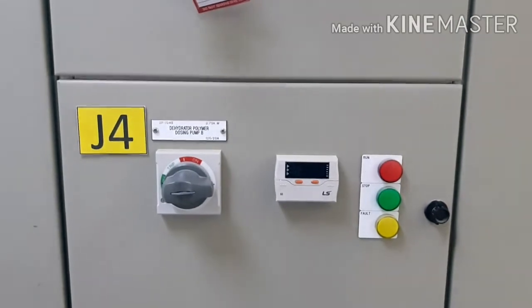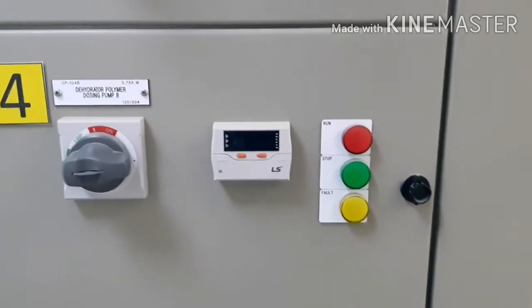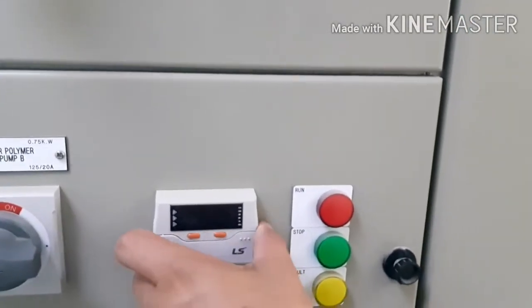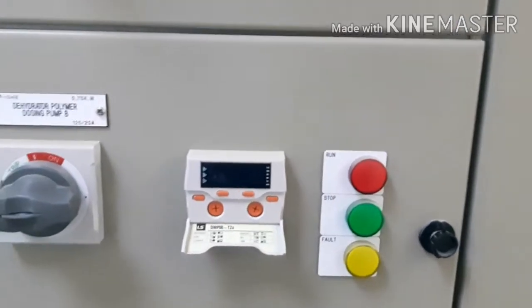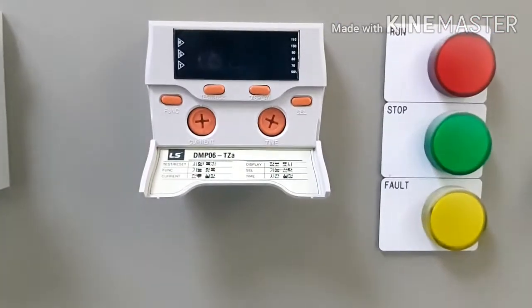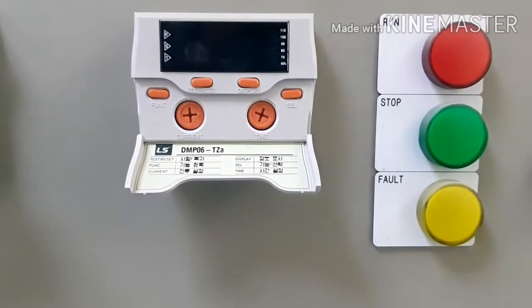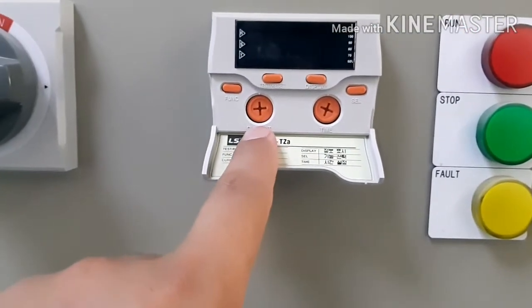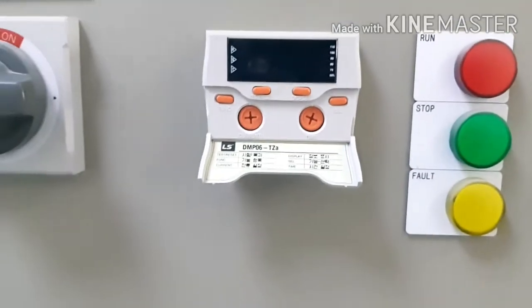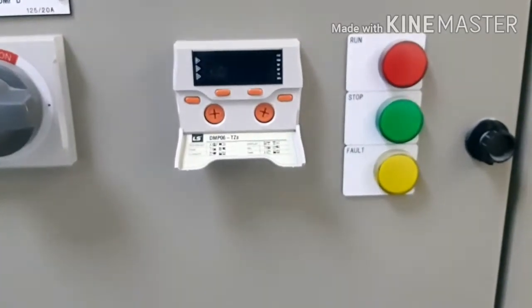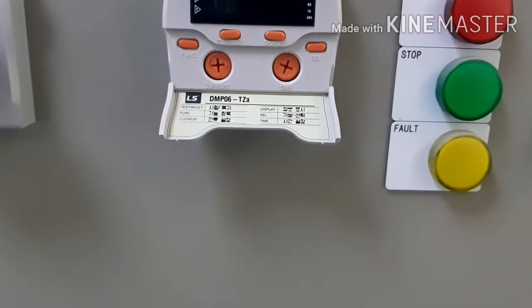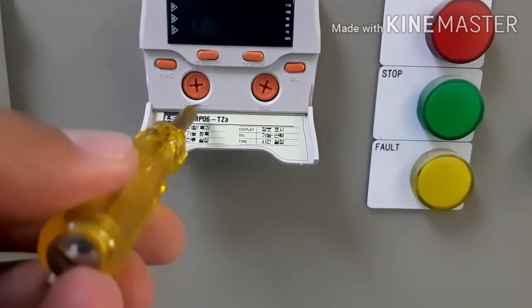Now I want to show you how to solve the problem. For example, if it's tripping, just check the motor rated current. If the motor rated current is, for example, 5 ampere, you should put it at 5 or 6, no problem. You should set it at or above the rated current, no problem, but not much higher, because it can damage your motor.